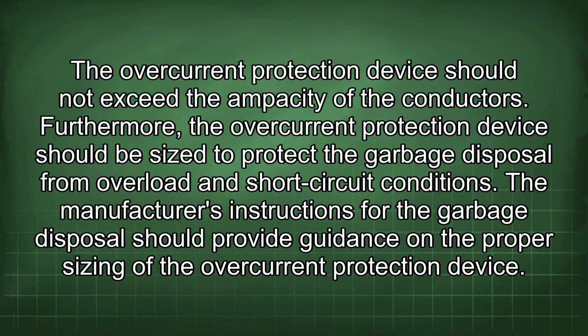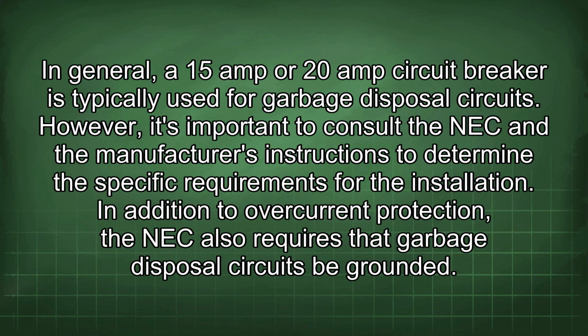Furthermore, the overcurrent protection device should be sized to protect the garbage disposal from overload and short-circuit conditions. The manufacturer's instructions for the garbage disposal should provide guidance on the proper sizing of the overcurrent protection device. In general, a 15 amp or 20 amp circuit breaker is typically used for garbage disposal circuits. However, it's important to consult the NEC and the manufacturer's instructions to determine the specific requirements for the installation.